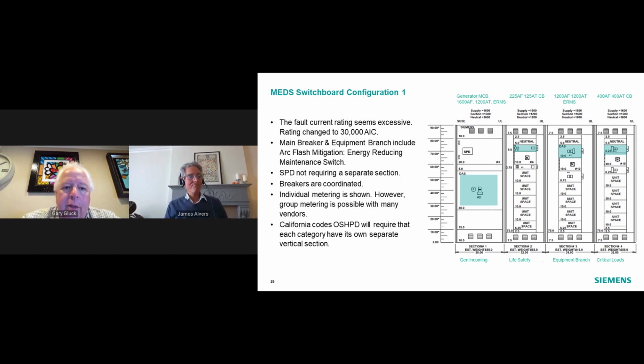All right, so switchboard configuration 1, just a couple of notes. The fault current rating seems excessive at 30,000 for the same reason that it was excessive in the earlier example, just due to the capacity of the generator. The main breaker and the equipment branch include arc flash mitigation, and we're using an energy reducing maintenance switch. The SPD is not required in a separate section. The breakers are coordinated, and individual metering is shown. However, group metering is possible with many vendors.